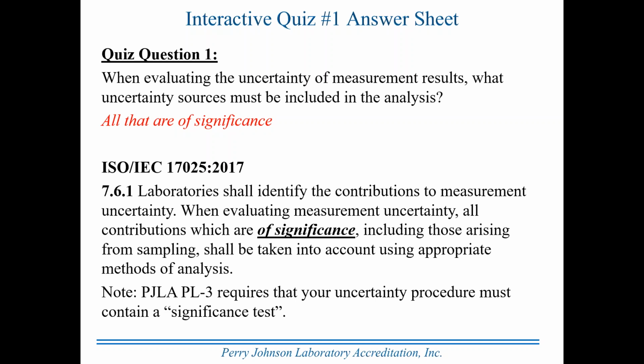There are literally thousands of potential contributors to uncertainty. And for instance, in calibrating mass, the phase of the moon is a contributor to uncertainty. If it is significant, it has to be included. In almost all instances, it is not significant, especially if you're working with commercial grade weights as opposed to high precision laboratory grade weights. The point is that, if you stand too close to the machine, that's potentially a contributor to uncertainty, depending on what the machine is doing. If it's a precision length measuring machine, anything that adds heat to it is a contributor to uncertainty.